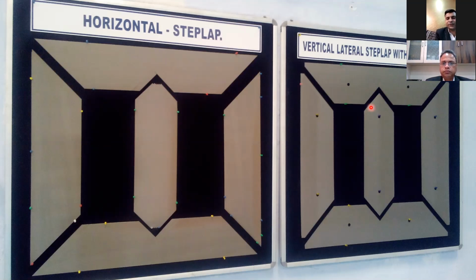Another beauty of this design is that it is very difficult to produce vertical step lap lamination with the help of manual miter cut, because this much accuracy and this much pitch distance cannot be maintained manually. If someone dares to produce vertical step lap with manual miter cut, he needs to do multiple changes in his machine settings. For example, if we have 5 pieces in our design, he needs to do setting at least 3 times, because we have 3 offsets, say 0, 5, and 10. So practically it is impossible to produce vertical step lap with manual miter cut.